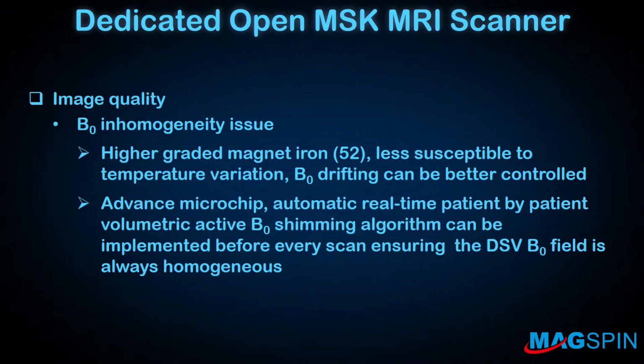One is the B0 inhomogeneities, but because of the material science that we have right now, we can use higher graded magnet iron like the 52, which is less susceptible to temperature variations, and B0 drifting can be better controlled. And the other thing is that because we have our own, more advanced spectrometers, we can do automatic real-time patient-by-patient volumetric active B0 shimming so that we can ensure that the DSV B0 field is always homogeneous before every scan.